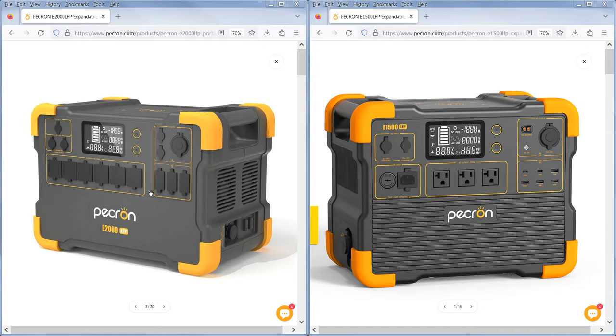So if you put a sump pump on or something very heavy, it better be quick, because that inverter will pop. Now the downside is if you don't expand the batteries to full capacity, which is 8 kilowatts here and about 7.5 kilowatts here, you have a bigger inverter on a smaller battery, and that drops the efficiency down.